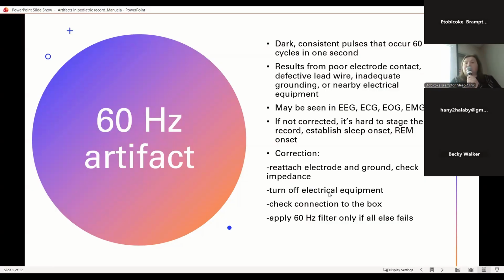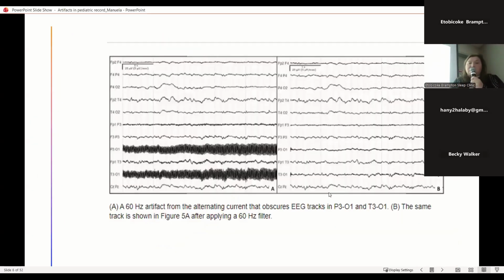As a correction, the technician should reattach the electrode and ground, check the impedance, turn off electrical equipment, check the connection to the box, but if all else fails, apply a 60 Hertz filter. So here a 60 Hertz filter was applied and the artifact corrected itself.